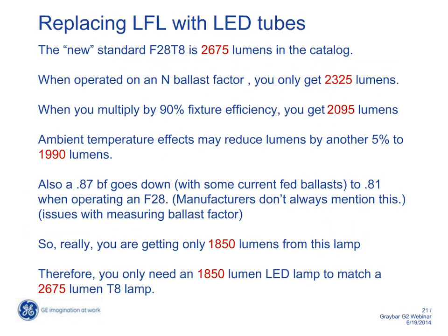So if you start comparing just light output in real applications, you need about maybe 1,900 lumens or so from an LED tube to match one of the most common 4-foot fluorescent choices. And again, we mentioned 2,100 or 2,200 lumens in the previous product. So clearly we're there from an equivalent light output standpoint, looking at tube per tube.